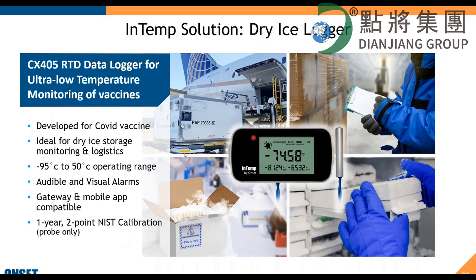And then we have the CX405, which is what we call our dry ice data logger. That could definitely be used for all the COVID vaccines, because most of the COVID vaccines need to be stored at -80 in a ULT freezer. It has an external probe that can go down to -95. Again, we have local alarming, gateway, and mobile app. It is delivered with a 1 year 2 point calibration certificate, and it's a 2 point for the probe.